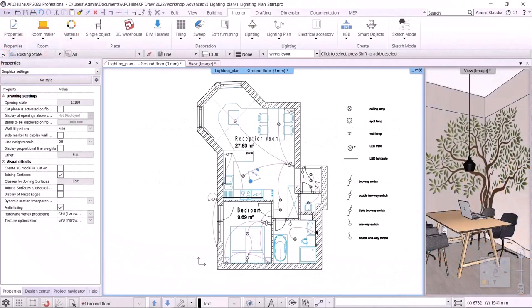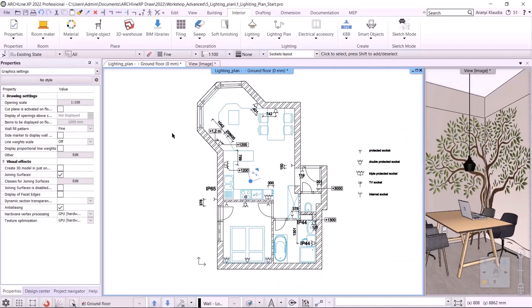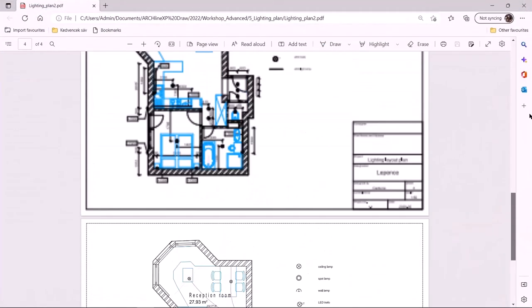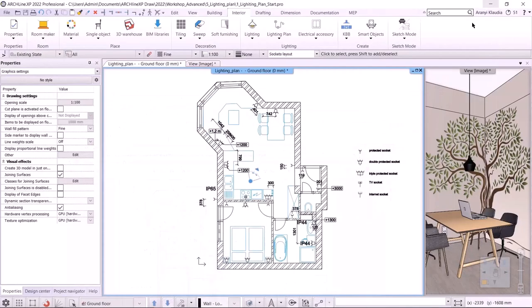The next will be the sockets layout plan. I switch over to the socket layout layer variation and turn on dimension sockets. Because I've already got some of the dimensions pre-made, we will just place the remaining dimensions. Let's take a look at the sockets layout plan on the PDF. We see that all sockets are dimensioned from the walls and we can see the height values as well. However, the height of the sockets is set to 300 mm from the covered floor level, and cases other than this are marked separately. So we will not mark all the heights, only those that deviate from 300 mm.